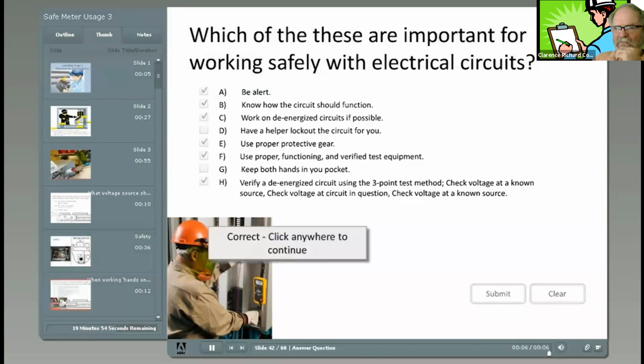The correct answers are A, be alert, B, know how the circuit should function, C, work on de-energized circuits if possible, E, use proper protective gear, F, use proper functioning and verified test equipment, and H, verify a de-energized circuit using the three-point test method. Check the voltage at a known source, check the voltage at the circuit in question, and check the voltage at a known source again.